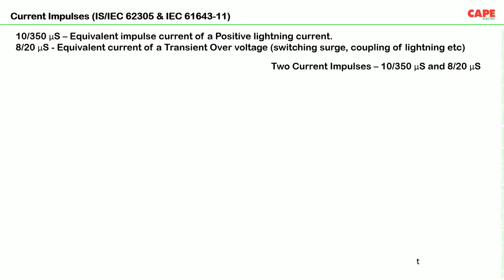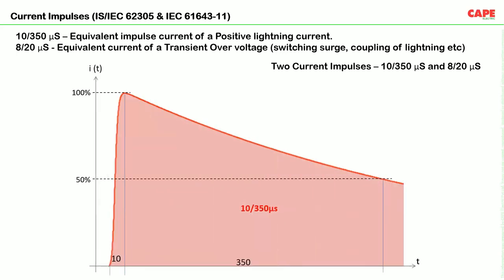Okay. So 8 by 20 microsecond is an equivalent current of a transient overvoltage. That means the surges which are generated due to some transient switching or some other coupling of lightning, those surges can be defined as 8 by 20 microsecond. I am going to explain the same through a graph also. See, this is the normal waveform of a 10 by 350 microsecond impulse. You can see this particular impulse goes from 0 to 100% of its peak value in 10 microseconds, and from 100% of its peak value to 50% of its crest value in 350 microseconds. Hence, it is called a 10 by 350 microsecond waveform.